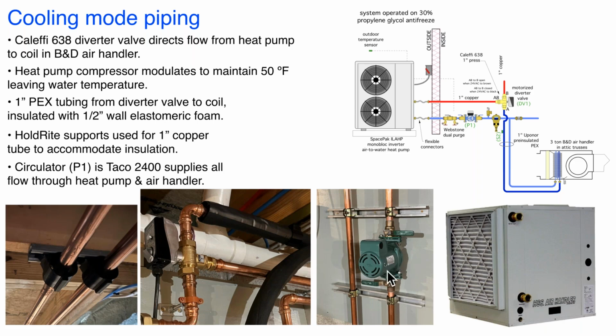So this is a Taco 2400 circulator. That's a fairly powerful circulator, but that circulator in cooling mode has to not only provide flow through the heat pump, but also has to take into account the head loss of the piping and the coil out here in the air handler. Here's that B&D air handler that was used to provide the chill water cooling.